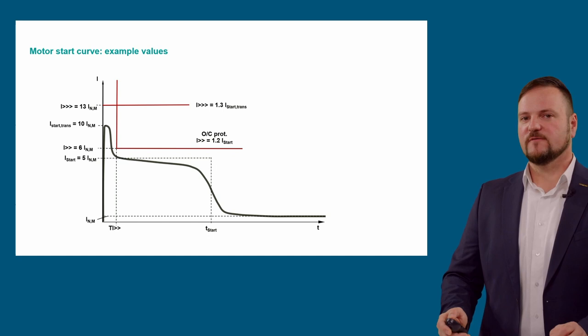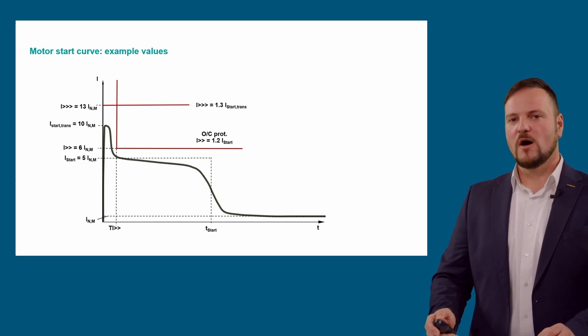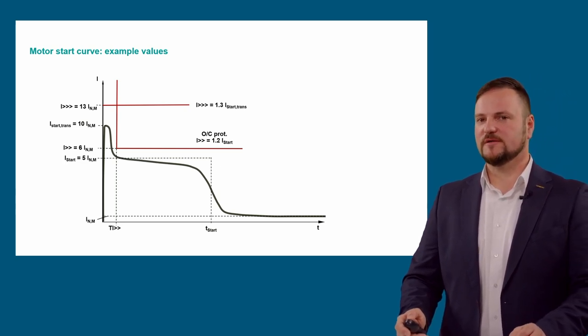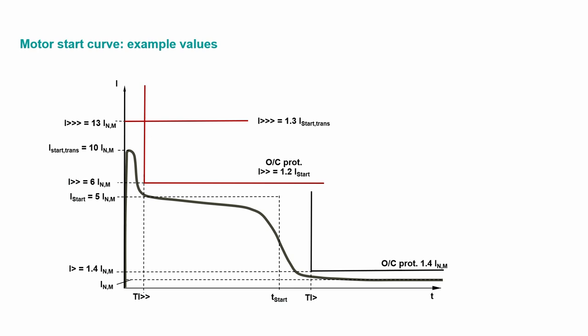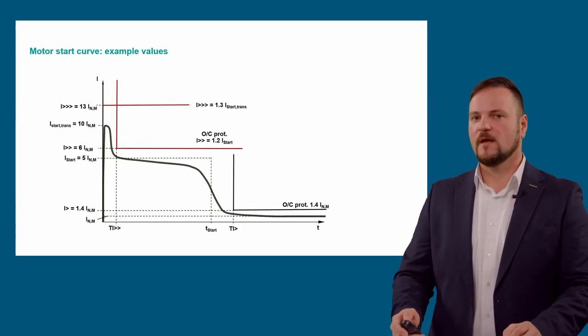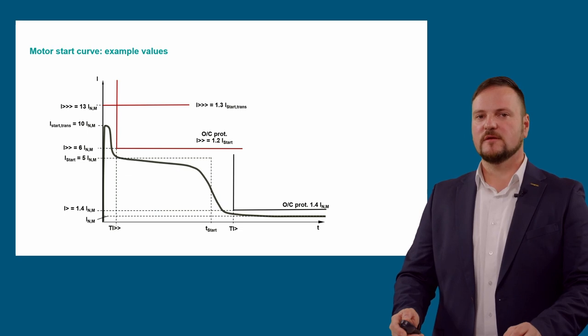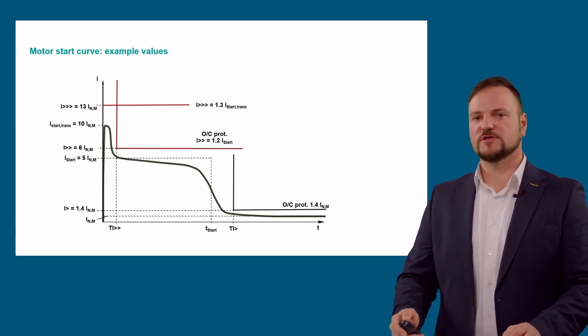Measurement of the fundamental can be set in order to filter out the DC components, which would be more considering the true RMS measurement. The third overcurrent stage could be applied just above the normal current to increase the sensitivity for short circuit current detection. However, delay time must be well above the maximum possible startup time, and it depends on this time if such a stage is really useful.